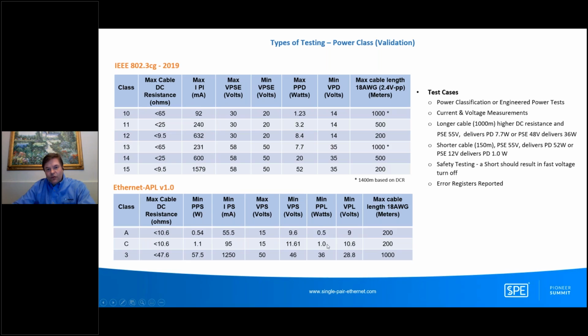500 milliwatts or 1 watt to the end devices. And then they have class 3 for their longer cable runs for trunks. They're using a 2.4 volt peak-to-peak model here when they transmit over trunks, and they can deliver up to 36 watts to the end device. So if you look at these power classes defined, they can support a wide variety of devices on the network.